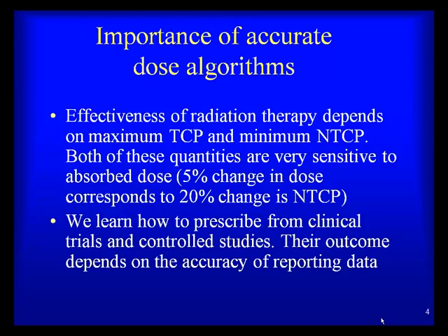Why is it important to have accurate dose calculation algorithms? The effectiveness of radiation therapy depends on maximizing tumor control probability and minimizing normal tissue complication probability. Both quantities are very sensitive to absorbed dose. We know from radiobiology that a 5% change in dose can correspond to as much as 20 or 25% change in normal tissue complication probability.